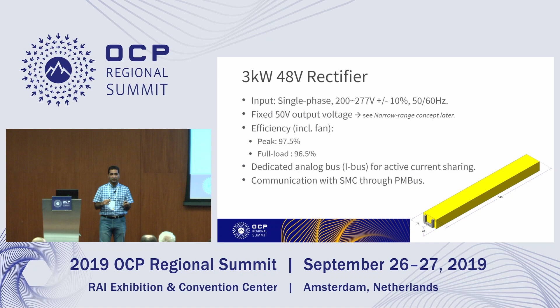And by the way, per spec, you can enable or disable it, or you can decrease or increase the amount of droop that you want. So that's all the detail there on the spec. And the communication between the rectifier to the SMC is through PM bus. It's a simple solution that I think is well established in the industry, and the goal is that the rectifiers should work with each other, even if the SMC is broken, it's not there, or any other way.